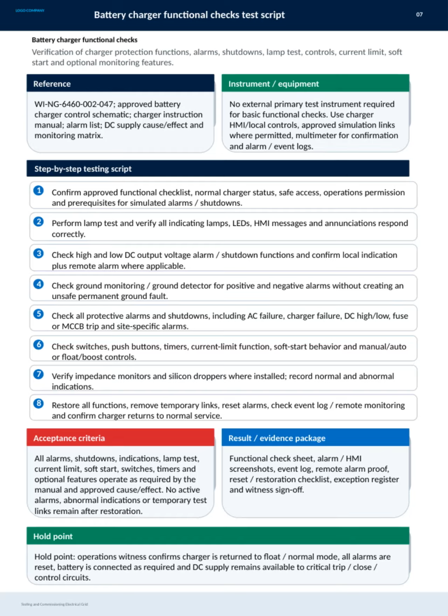This battery charger functional checks test script is designed to ensure that every critical aspect of the charger's operation is verified thoroughly. We start by confirming that all prerequisites, safety measures, and permissions are in place for testing simulated alarms and shutdowns. Then, we perform a lamp test to verify that all indicators, LEDs, and HMI messages respond correctly. Next, we check the high and low DC output voltage alarms and shutdown functions, confirming both local and remote indications.